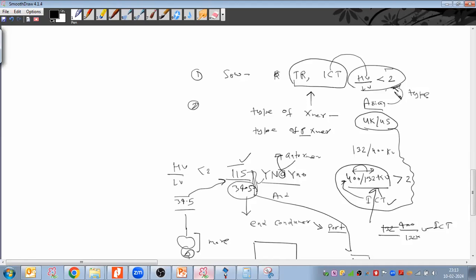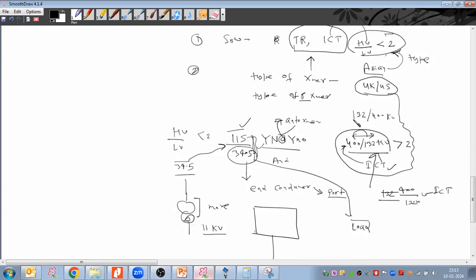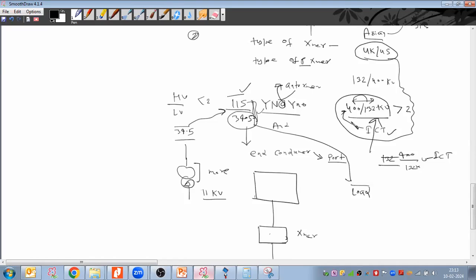So yes, since there is no effect of changing harmonics, that is the reason maybe they use it, because you are not connected with the load directly. So what we do is, when we come with the load, if I connect an auto transformer, then in the auto transformer your HV and LV both are electrically connected, right? Yes, correct. So whatever harmonics you are putting, that will come in the HV winding, and that will feed to the HV system as well, which should not be allowed, which we should avoid.